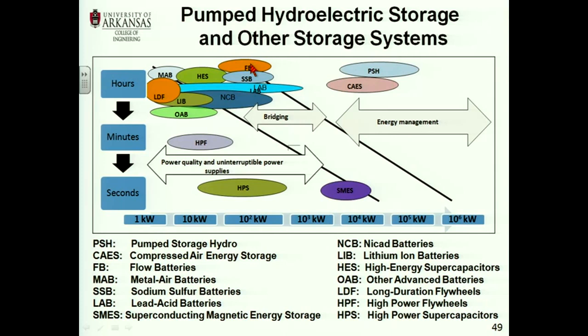When it comes to battery, you have to take into account the return trip efficiency. What is the return trip efficiency? You have to charge the battery. Think of the model of a battery, the simplest one, is like your infinite bus, right? You have the ideal voltage source, and you have the short circuit impedance.